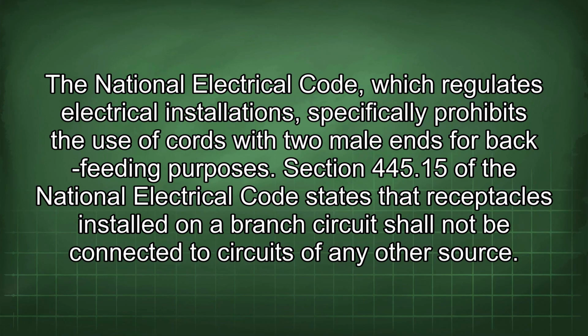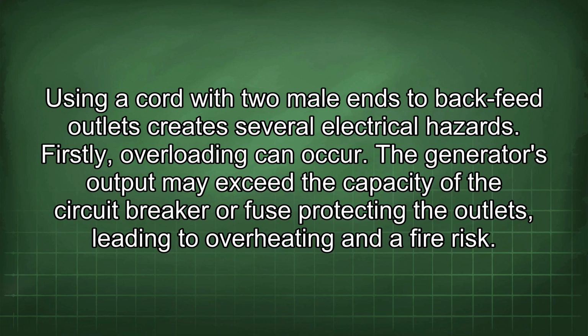The National Electrical Code, which regulates electrical installations, specifically prohibits the use of cords with two male ends for backfeeding purposes. Section 445.15 of the National Electrical Code states that receptacles installed on a branch circuit shall not be connected to circuits of any other source. Using a cord with two male ends to backfeed outlets creates several electrical hazards.